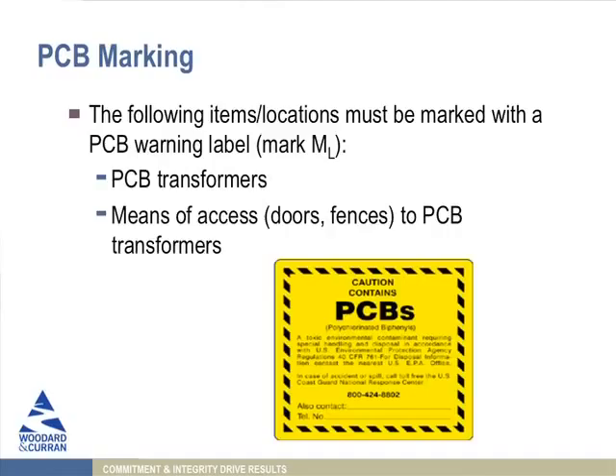As a best management practice, it's good to mark all the other transformers so you know this doesn't apply to them. So if you've changed out the oil, what used to be a PCB transformer now no longer is, because the oil has all been changed out. Mark it as non-PCB so everybody knows you no longer have to worry about this requirement.